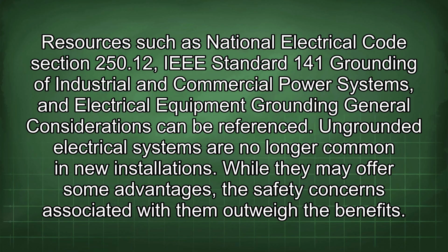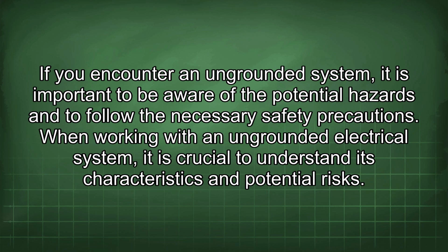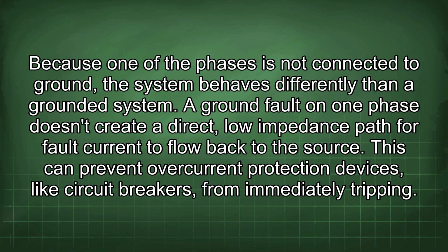Ungrounded electrical systems are no longer common in new installations. While they may offer some advantages, the safety concerns associated with them outweigh the benefits. If you encounter an ungrounded system, it is important to be aware of the potential hazards and to follow the necessary safety precautions. When working with an ungrounded electrical system, it is crucial to understand its characteristics and potential risks. Because one of the phases is not connected to ground, the system behaves differently than a grounded system.